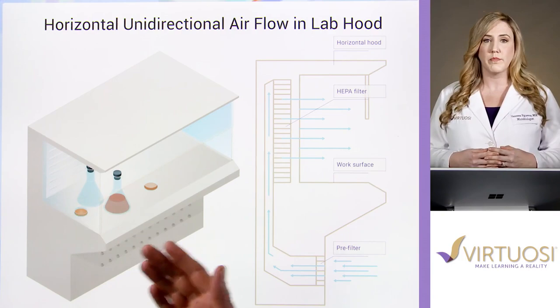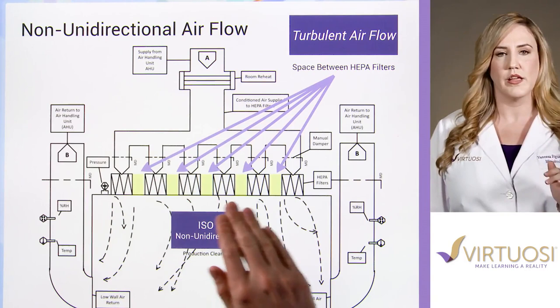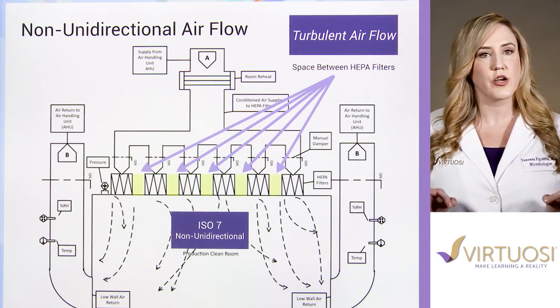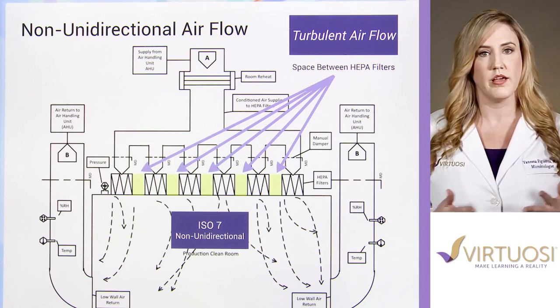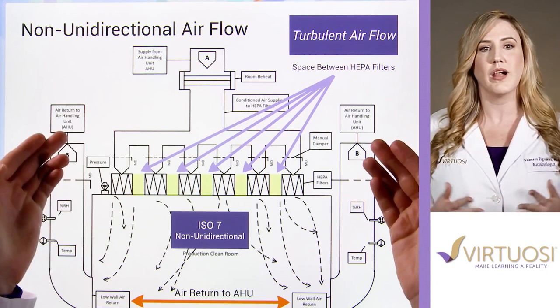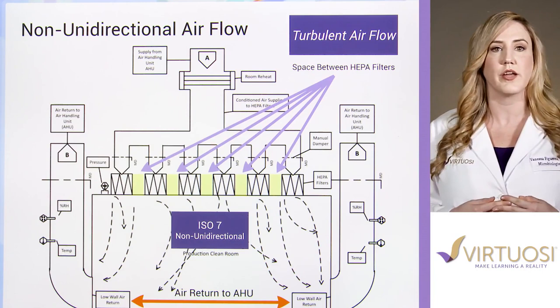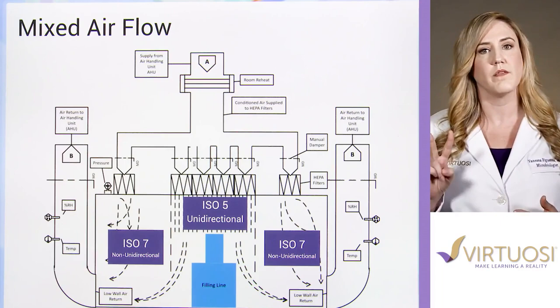Unidirectional airflow can be either vertical or horizontal depending on the work to be performed. Non-unidirectional airflow is created by having HEPA filters not adjacent to each other, with ceiling space where there are no filters. Non-unidirectional airflow is also referred to as turbulent airflow. In zones surrounding ISO 5 and preparatory areas such as ISO 8, the principal means of particulate control is via dilution. The nature of turbulent airflow means that particles can move in multiple directions. Mixed airflow is a combination of the two types in the same manufacturing space.